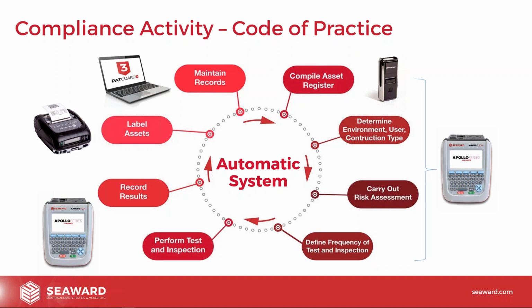Now it does depend on what scale of system you've got. If you're testing one or two items every few months, you probably don't need this type of system. But once you start getting over a few hundred assets, you do see the savings at the back end come from doing this. From a compliance point of view, and from a Seaward point of view, we have solutions all the way through, from our Prime Test 50, a very basic go, no go PAT checker, all the way up to the Apollo 600 with a camera and all the things in there. So it's about getting the right solution for the customer.